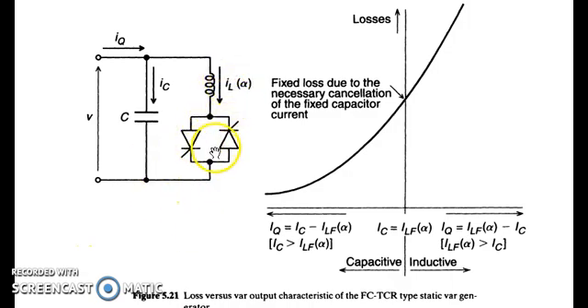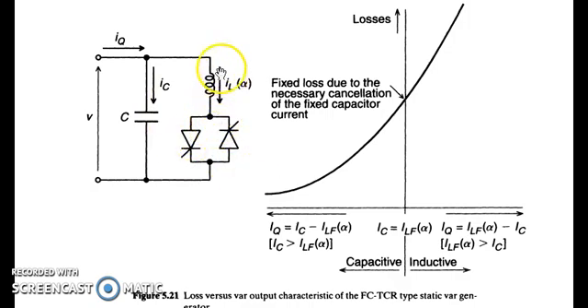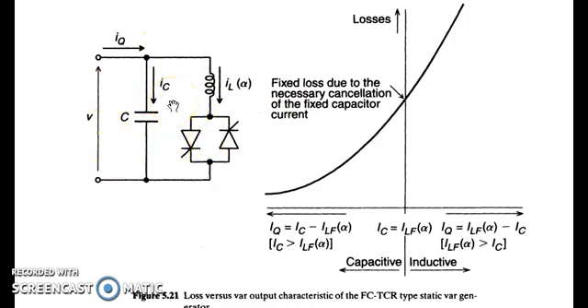In this figure, a thyristor switched or thyristor controlled reactor is coupled with a fixed capacitance. This capacitance is always within the circuit — it cannot be switched on or off. So the only controllable component is the inductive component. When there is an excess of reactive power, which arises in cases of low loads, we can control the switching of the thyristors to bring more of the inductive component into the circuit so that it consumes more of the excess reactive power.